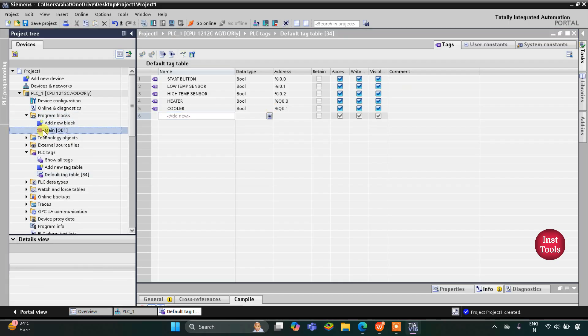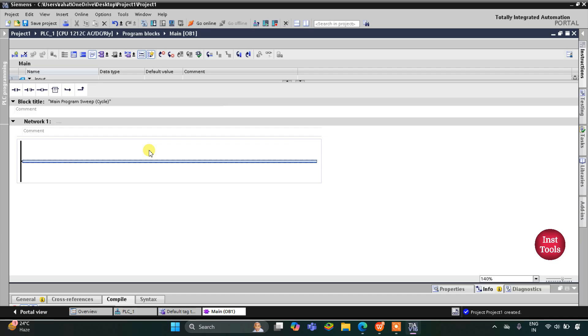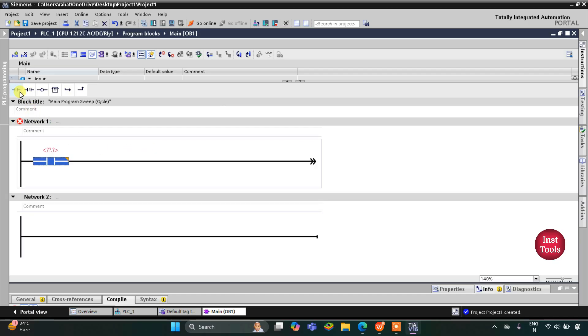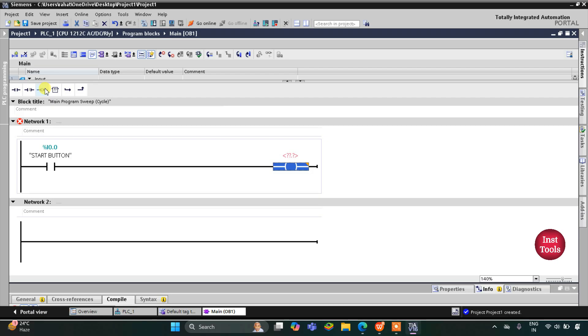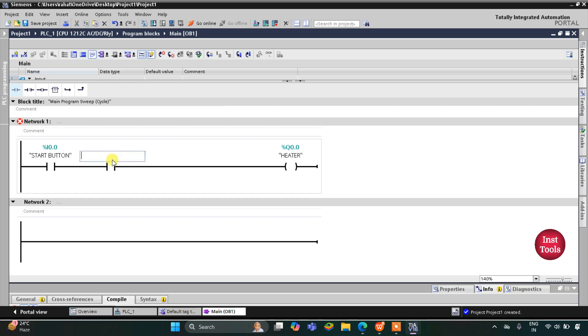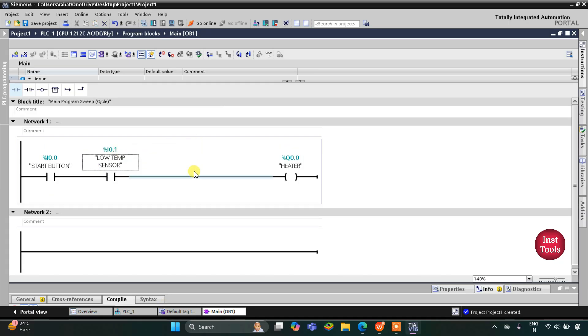Now we go to program blocks and then main OB1 where we will draw the ladder diagram. First I will insert a normally open contact for the start button, and then I will insert a coil for the heater. This heater should turn on when the low temperature sensor detects that the temperature is low, so I will insert a normally open contact for the low temperature sensor.